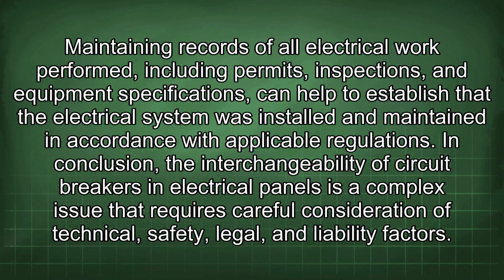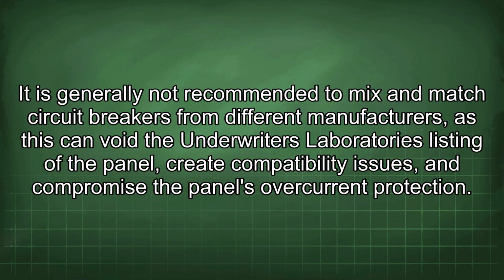In conclusion, the interchangeability of circuit breakers in electrical panels is a complex issue that requires careful consideration of technical, safety, legal, and liability factors. It is generally not recommended to mix and match circuit breakers from different manufacturers, as this can void the Underwriters Laboratories listing of the panel, create compatibility issues, and compromise the panel's overcurrent protection.